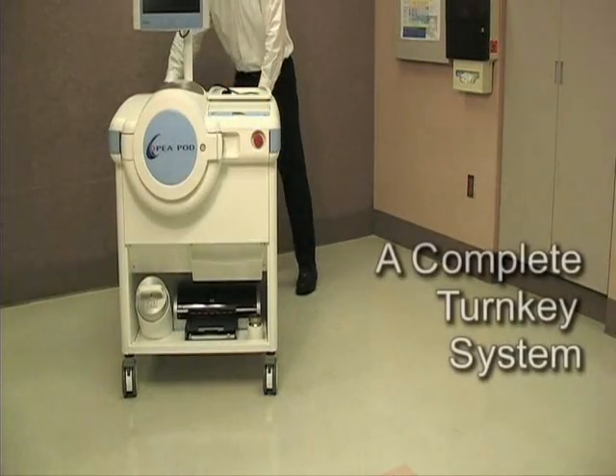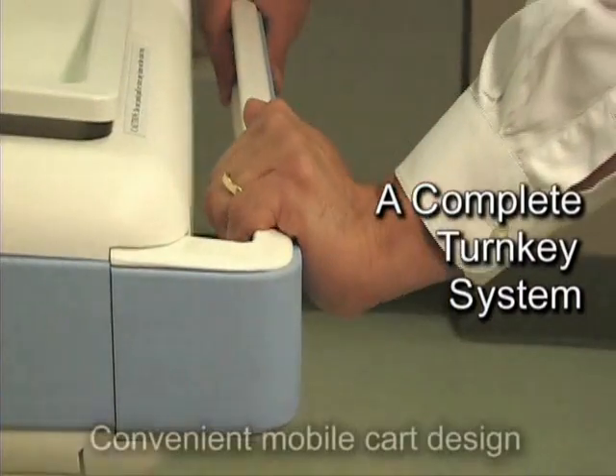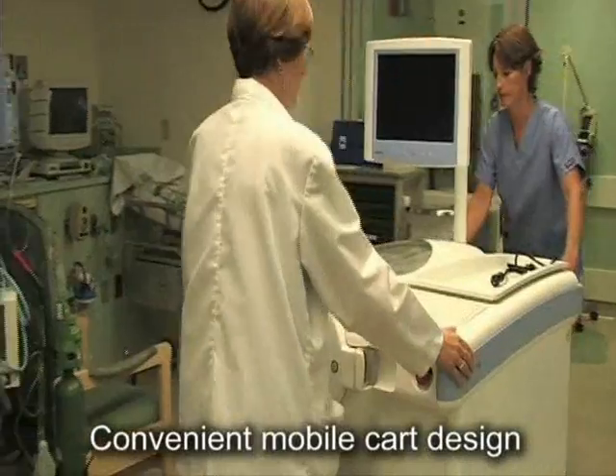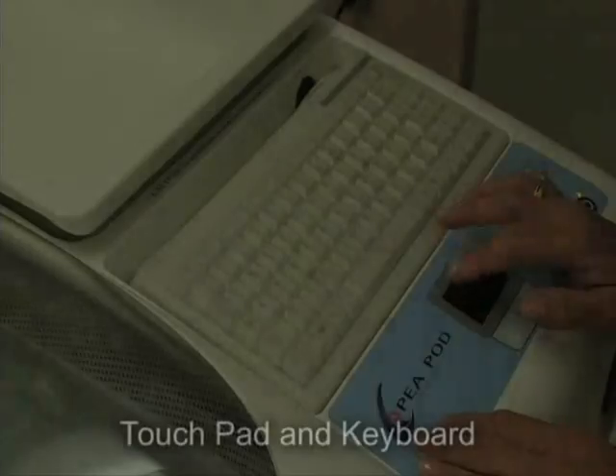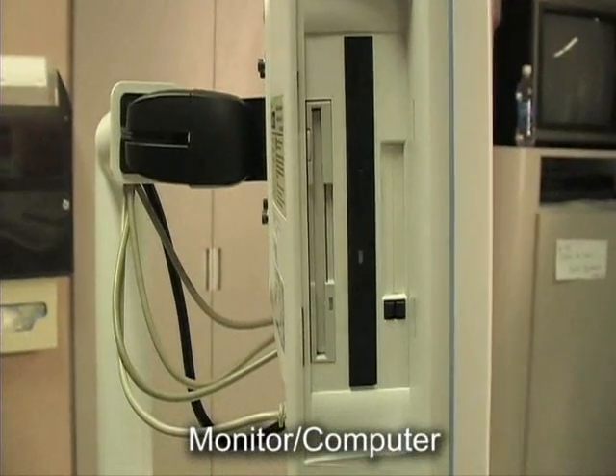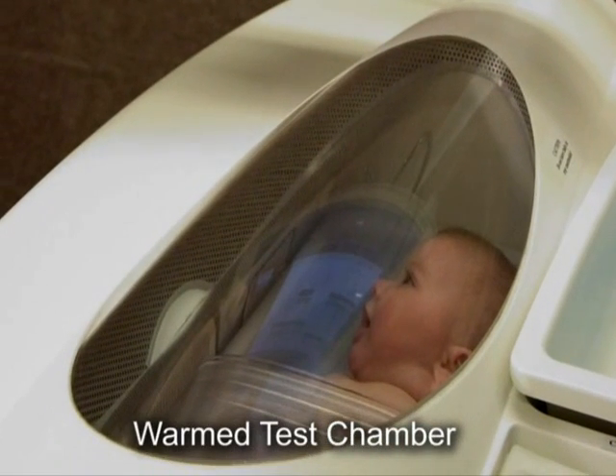Each PEA POD is a complete turnkey system. Everything needed to operate the unit is included, and the convenient mobile cart design allows the PEA POD to be rolled to the infant for bedside assessments or to other areas as needed. The PEA POD is operated using a touchpad, keyboard, and an integrated monitor computer. Its major components consist of a scale for measuring body mass and a test chamber for estimating body volume.